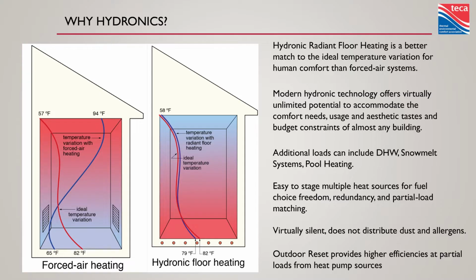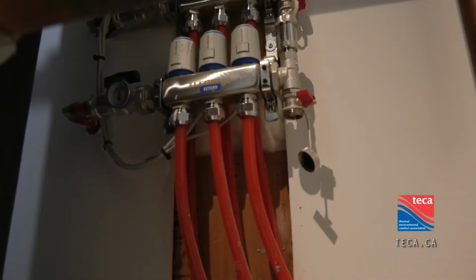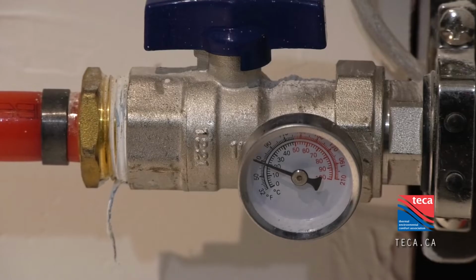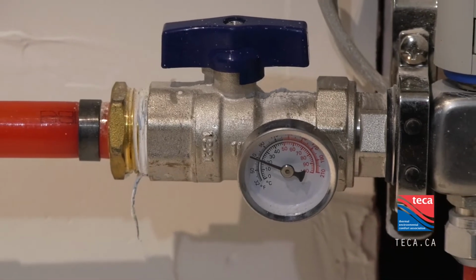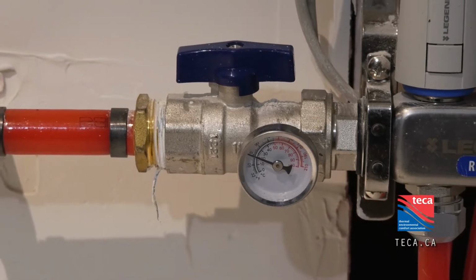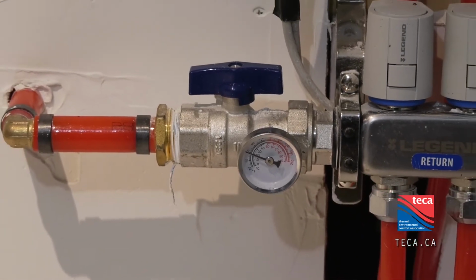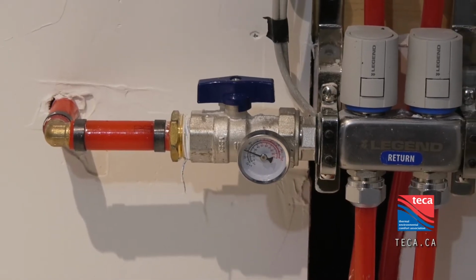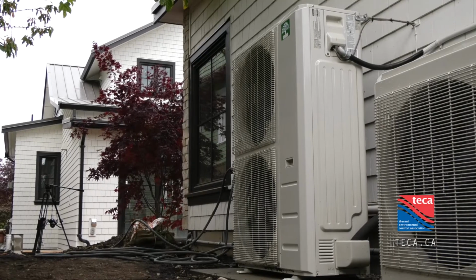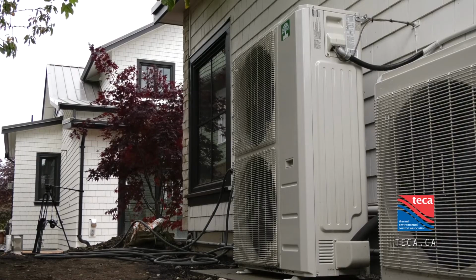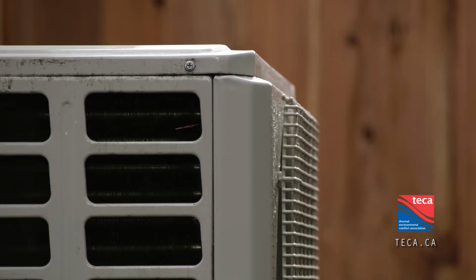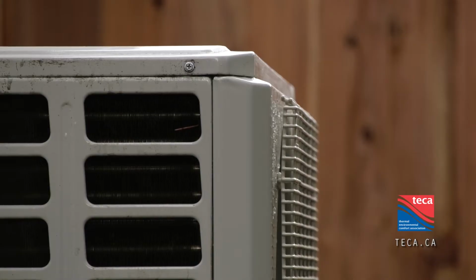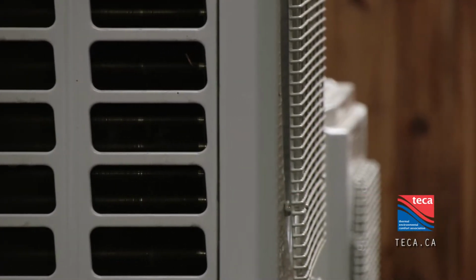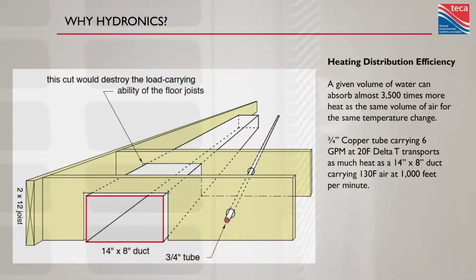Radiant floor is virtually silent, a very, very popular thing. But I'm not here to sell you on radiant. It's already happening, it's everywhere. But a key difference with air-to-water heat pumps is temperature control. If I can drill one thing home tonight, it's about delivered water temperatures and their effect on capacity and efficiency in a heat pump. We can heat with very low temperatures with radiant floor heating, much lower than anyone would be comfortable with if that was the air temperature coming out of a forced air system. So we have an opportunity to deliver very high efficiencies from our equipment because it's such a low temperature heat distribution medium.